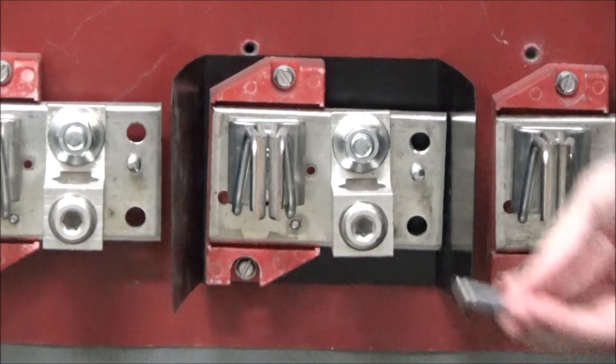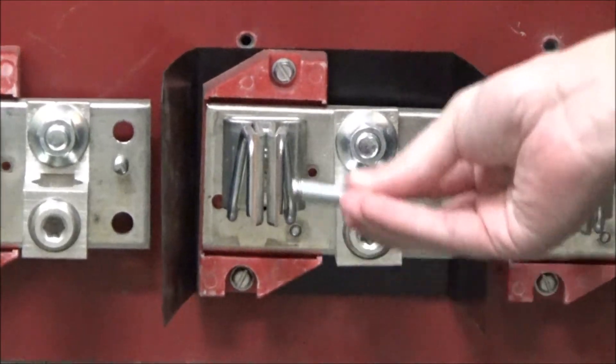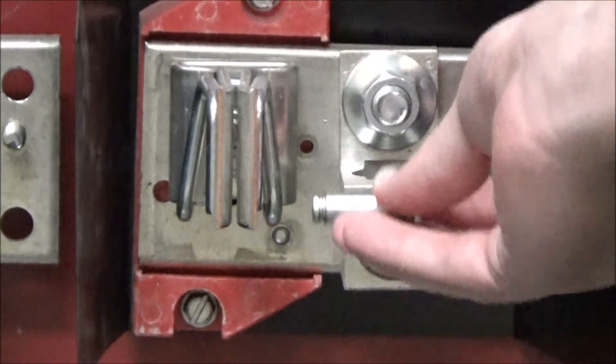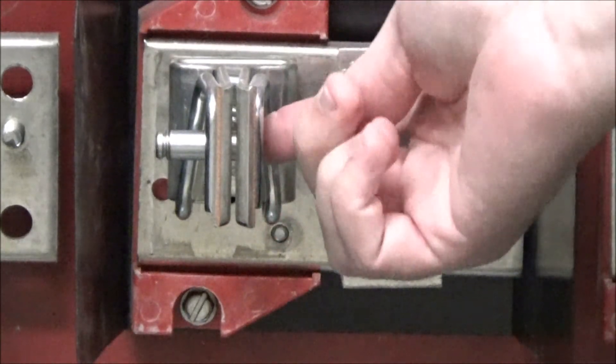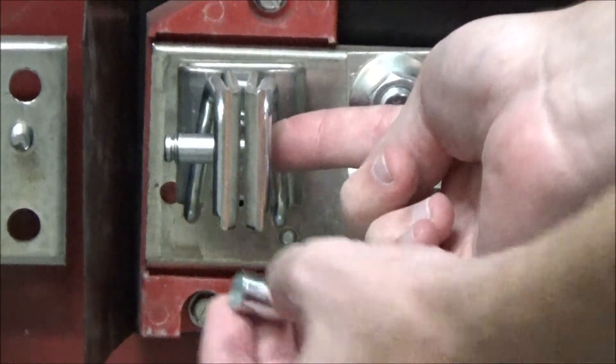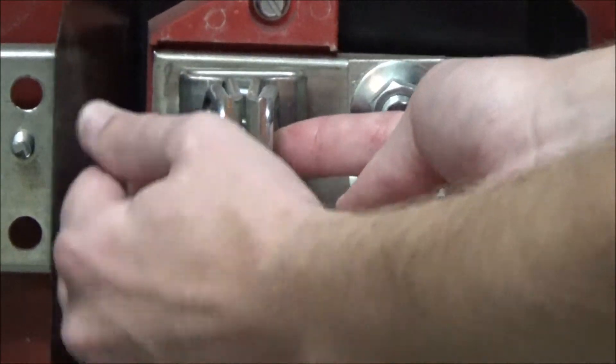To install the class R fuse kit you will slide the pin into the hole in the fuse clip from the lug side and then push the collar onto the pin firmly like so.